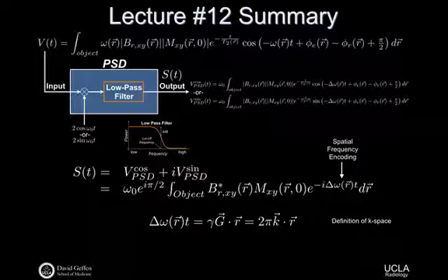So our goal was to get towards doing what's called quadrature detection, whereby we combine the two phase-sensitive detected signals. We have some signal as a function of time, and we're going to combine those two detectors. We had a sine detector and a cosine detector. Our magnetization is actually precessing around. The sine detector has you looking at the signal oscillating back and forth this way. The cosine detector has you looking at the signal the other way and picking up the oscillation in the other dimension. So there are two components to that oscillation because it's a precession in the transverse plane.